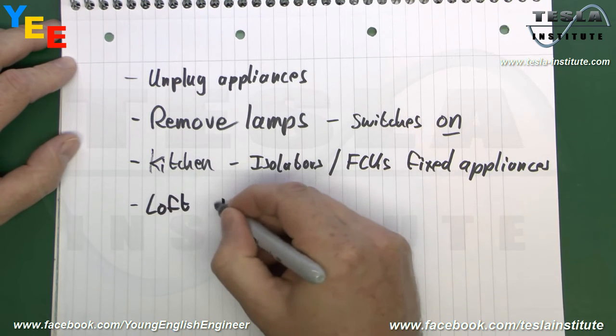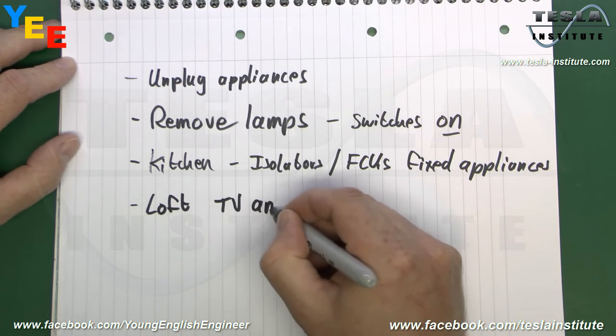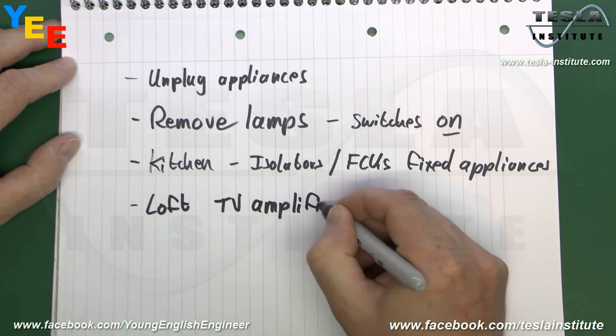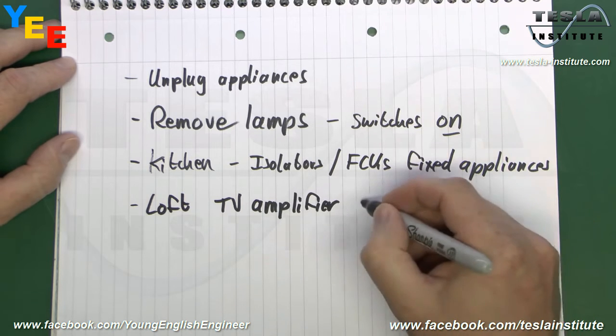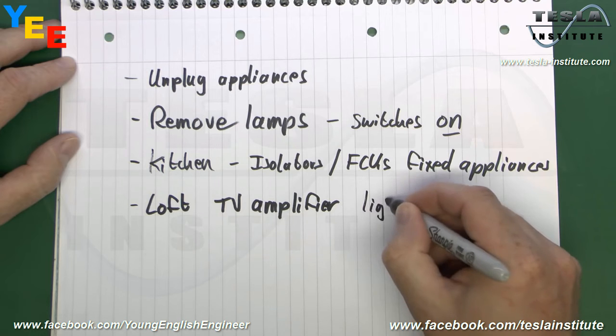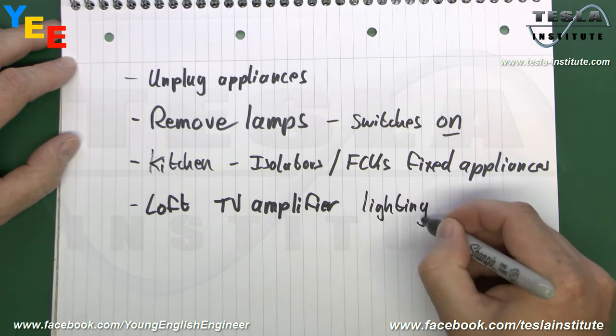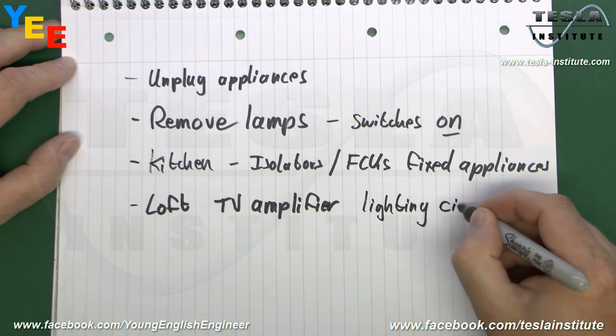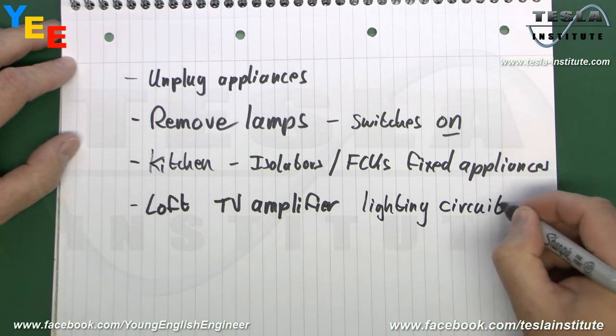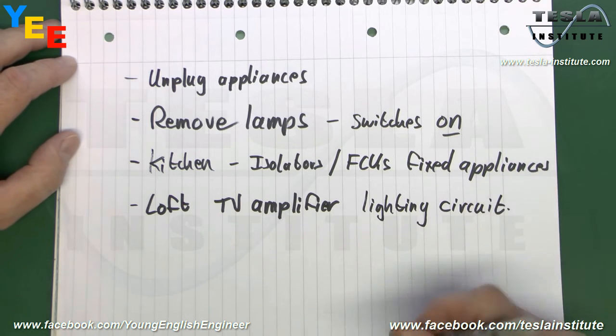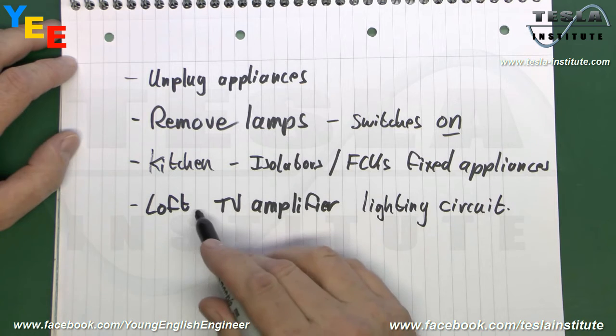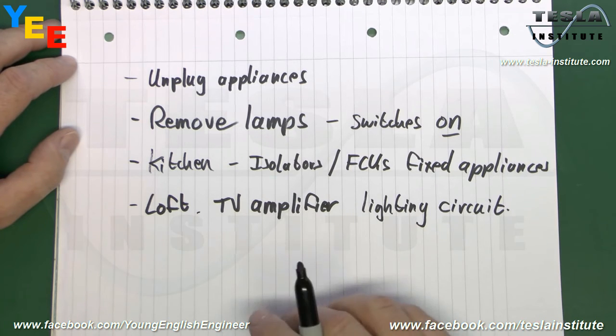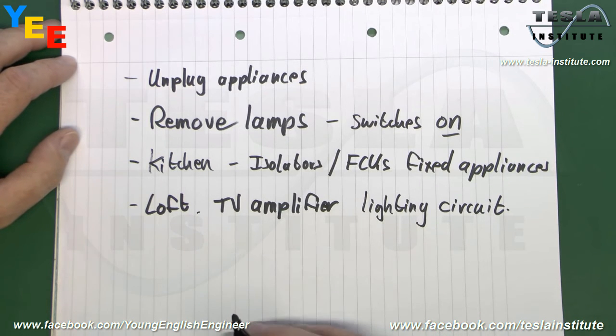You may find things like TV amplifiers. These are commonly attached to the lighting circuit, mainly because that's the only circuit that's usually in the loft. So if you find a lighting circuit that's got some apparent load on it, even though you've removed all of the lamps and everything, then have a look in the loft, because maybe one of those television amplifiers or aerial amplifiers is stuck in there, attached to the lighting circuit.